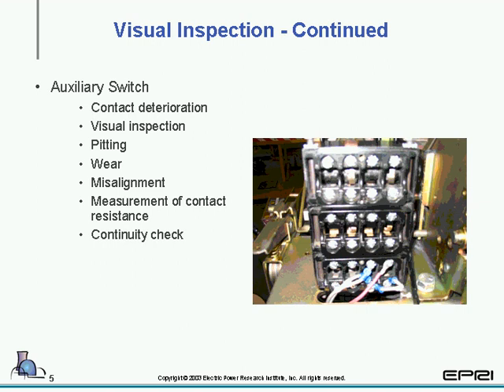We're taking a look at auxiliary contacts again. One of the other items we want to talk about is what you should expect to see: with the contacts in the closed state, 1 ohm or less, and with the contacts in the open state, infinity or very high. Typically, A's follow the main contacts. So when the main contacts are closed, A contacts are closed and B's are open. When the breaker is open, B contacts are closed and A's are open.